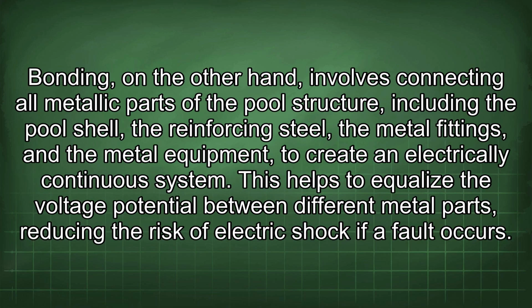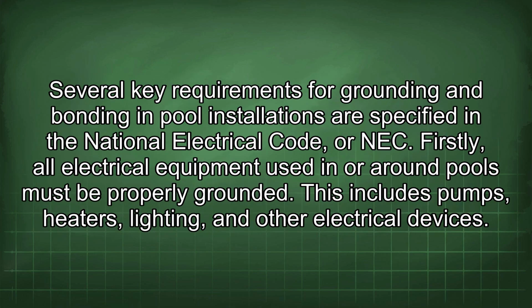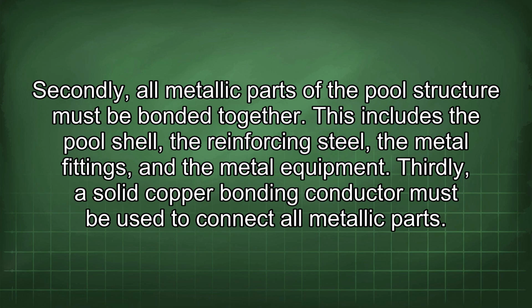Bonding, on the other hand, involves connecting all metallic parts of the pool structure, including the pool shell, the reinforcing steel, the metal fittings, and the metal equipment, to create an electrically continuous system. This helps to equalize the voltage potential between different metal parts, reducing the risk of electric shock if a fault occurs. Several key requirements for grounding and bonding in pool installations are specified in the National Electrical Code, or NEC. Firstly, all electrical equipment used in or around pools must be properly grounded. This includes pumps, heaters, lighting, and other electrical devices. Secondly, all metallic parts of the pool structure must be bonded together. This includes the pool shell, the reinforcing steel, the metal fittings, and the metal equipment.